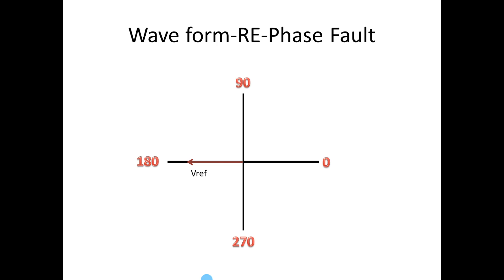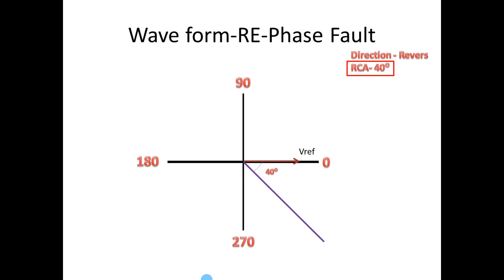Now we are going to see the reverse directional earth fault operating region. For reverse directional, V reference should be opposite to the forward V reference, and here also RCA is 40 degrees. We take V reference as reference, make 40 degrees towards the clockwise direction and draw a line — this line is known as MTL. To get this angle, subtract 40 from 360 degrees; we get 320 degrees — draw a line here.